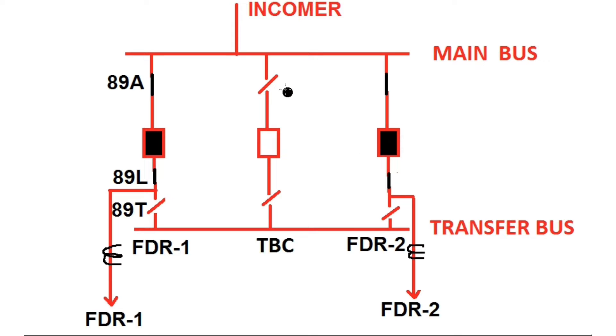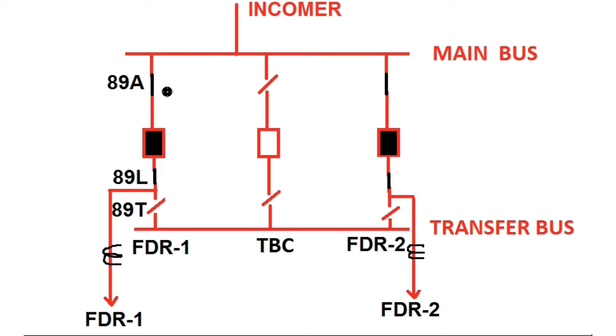This is the same for feeder 2, and this is the TBC bay — that is the transfer bus coupler bay. 89A is the main bus side isolator and 89T is the transfer bus side isolator for the TBC bay. It is called the TBC bay or transfer bus coupler bay because it couples the main bus with the transfer bus. Now, feeder 1 and feeder 2 are both taking power from the main bus via 89A and 89L in closing condition and the breaker is closed.